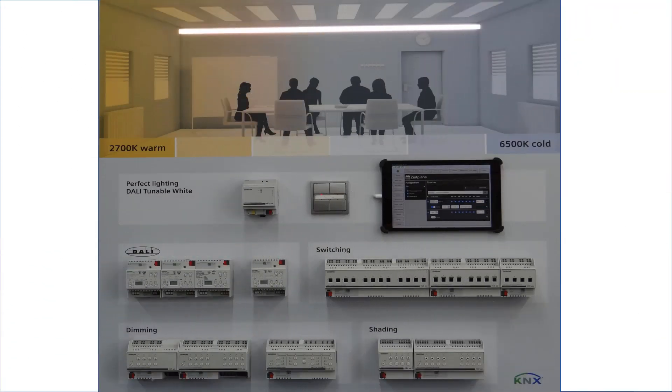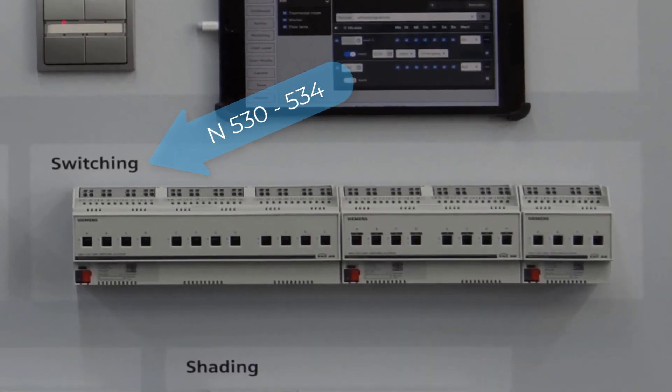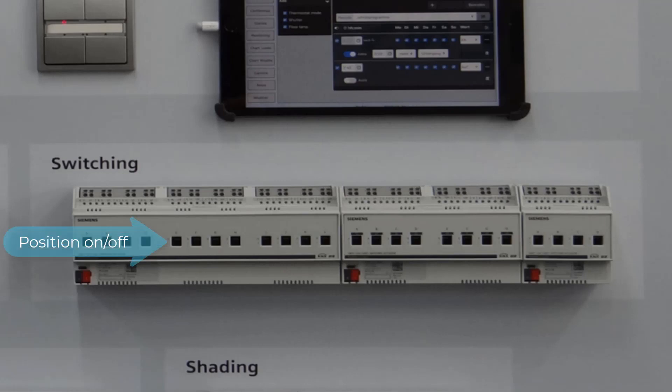About two years ago, Siemens began designing and launching a completely new family of DIN rail-mounted devices. It started with a continuous series of switch actuators. The scaled actuators are available with four, eight, and twelve switching channels, and have module widths of four, eight, and twelve. The portfolio is designed for various rated currents from 6 amperes and 10 amperes up to very high currents of 20 amperes. The switching of capacitive, inductive, and resistive loads is possible. At the front of the device, the actuators have a mechanical switch position indicator with manual operation.